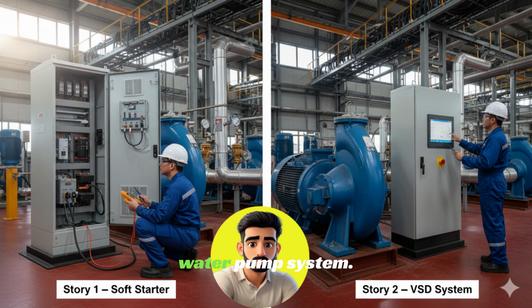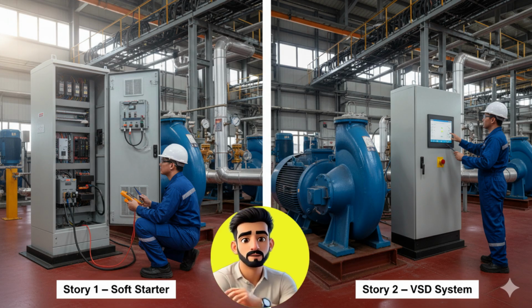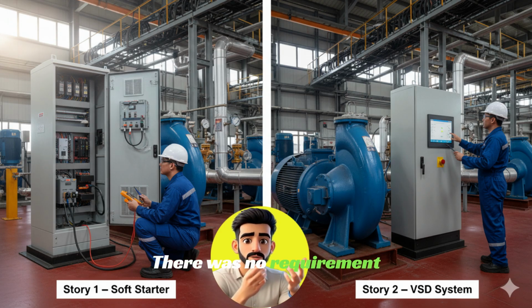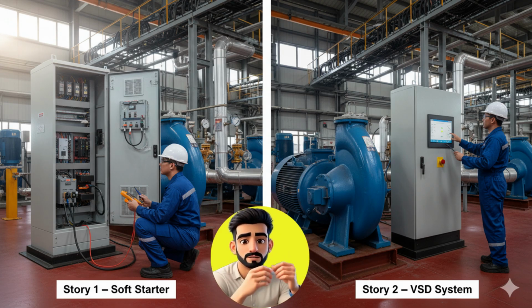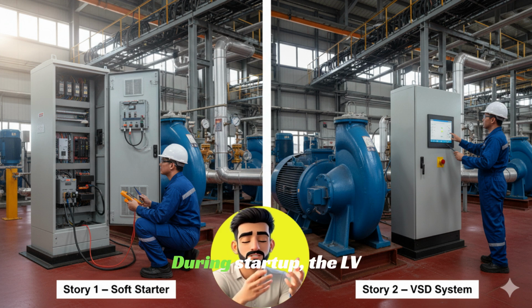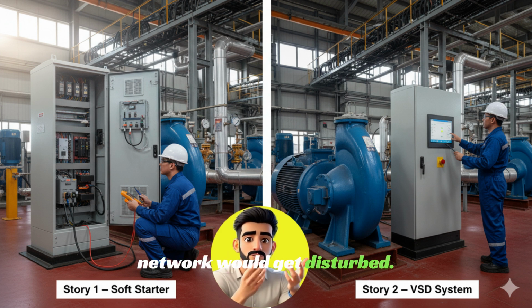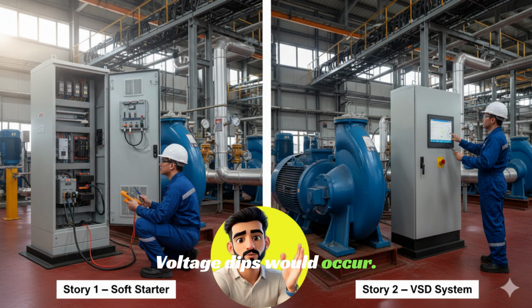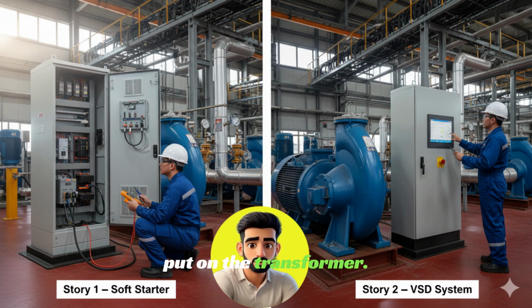There was a chilled water pump system. The pumps operated only on an on and off logic. Flow balancing was done manually with valves. There was no requirement to change the speed in the process. There was only one problem. During startup, the LV network would get disturbed. Voltage dips would occur and stress would be put on the transformer.